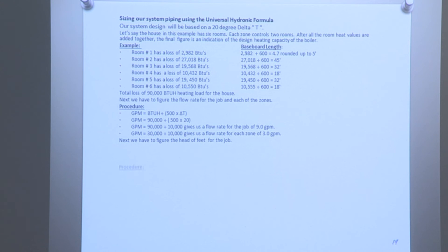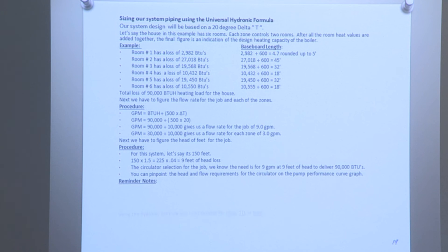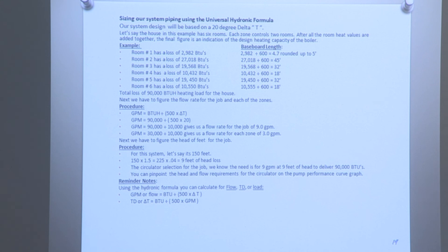Next, we figure the head in feet for the job. For this system, the longest loop is 150 feet. 150 times 1.5 equals 225 feet times 0.04 equals 9 feet of head. For circulator selection: we need 9 gallons per minute at 9 feet of head to deliver 90,000 BTUs. You can pinpoint the head and flow requirements on the pump performance curve graph. Reminder: using the hydronic formula, you can calculate flow, temperature difference, or load. GPM equals BTU divided by 500 times delta T; delta T equals BTU divided by 500 times GPM; and BTU equals 500 times delta T times GPM.